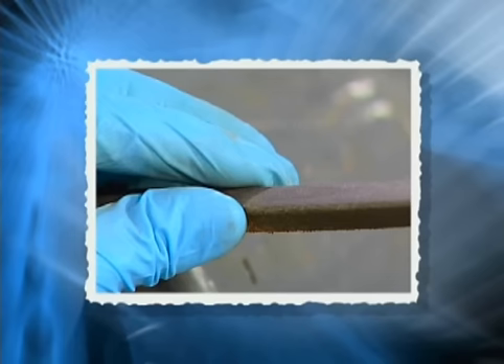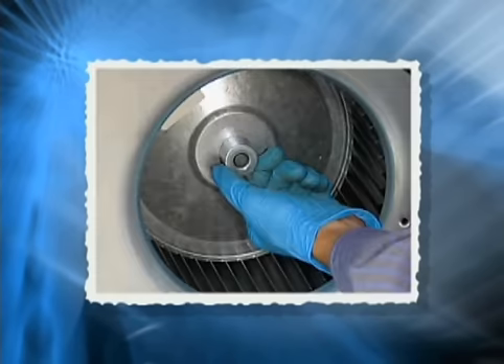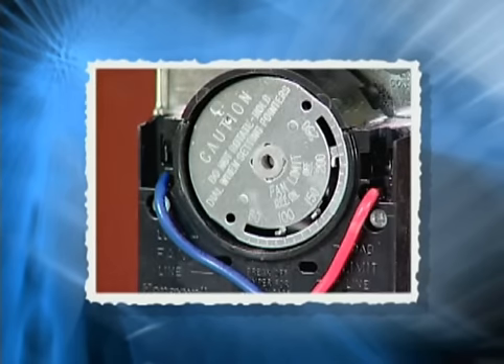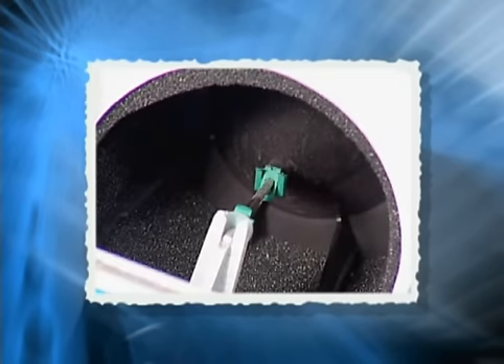Check the condition and tension of the fan belt and replace or adjust as required. Check the blower mountings and bearings for excessive wear. Then properly reinstall the blower compartment door. Finally, check the settings where the blower cycles on and off. If there is a humidifier, check it for proper operation, water leaks, and mineral buildup.